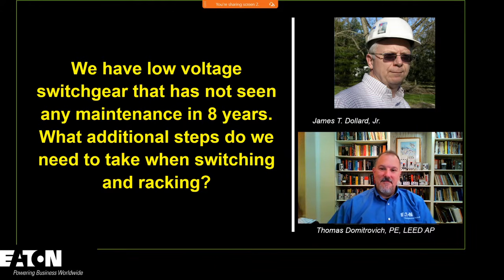But then I would get into it, because I would try to make them understand that this is not something to just get involved with and jump right into the equipment. Although, in my experience, I've seen this happen over and over again, because prior to training, the men and women in the field don't understand how to properly perform an arc flash risk assessment. When we perform an arc flash risk assessment and you're using the tables, one of the other things you need to do is determine the operating condition of that device and its condition of maintenance. And you have to understand what equipment requires maintenance and when that maintenance is required.